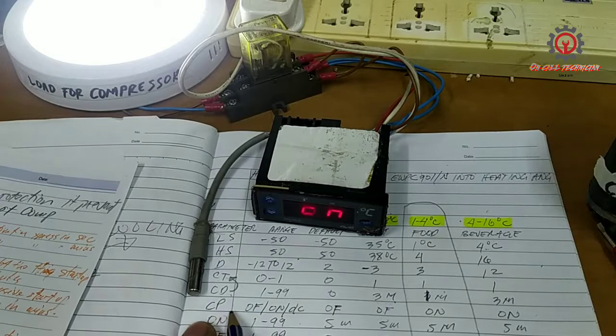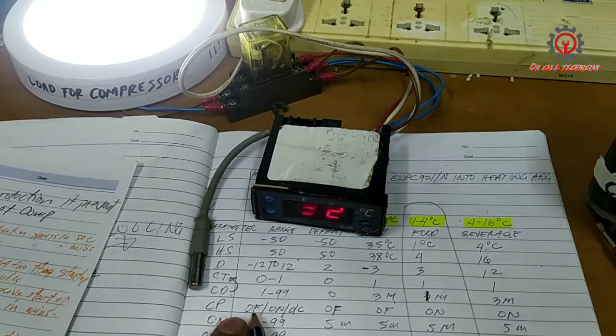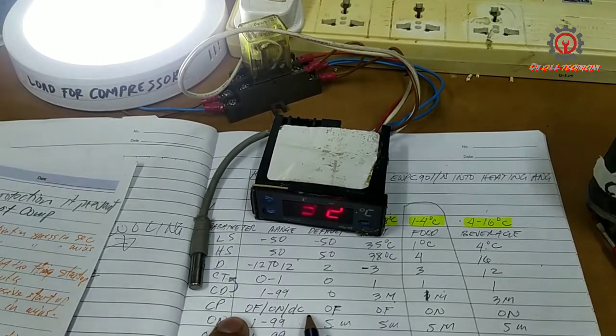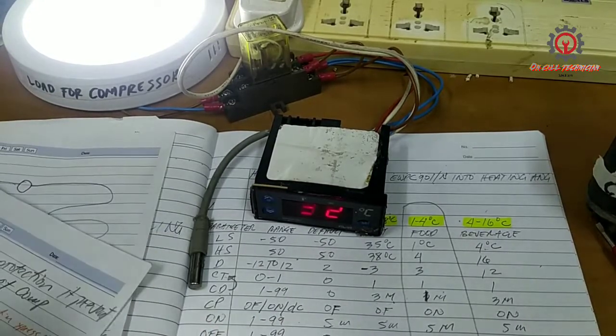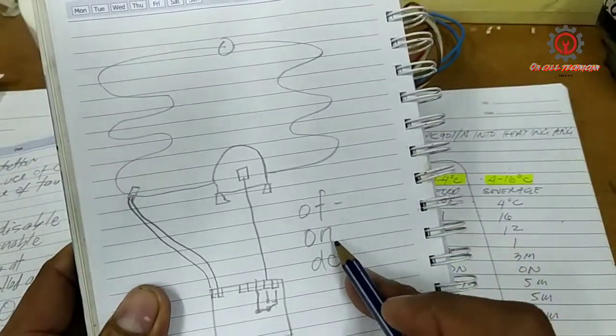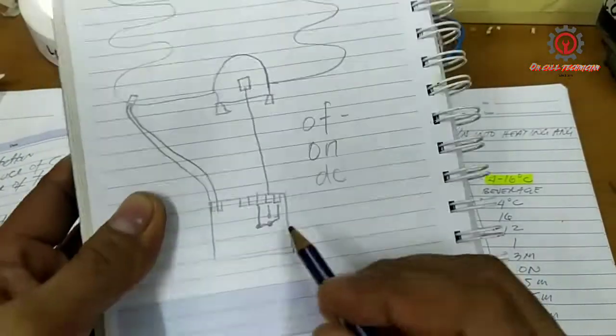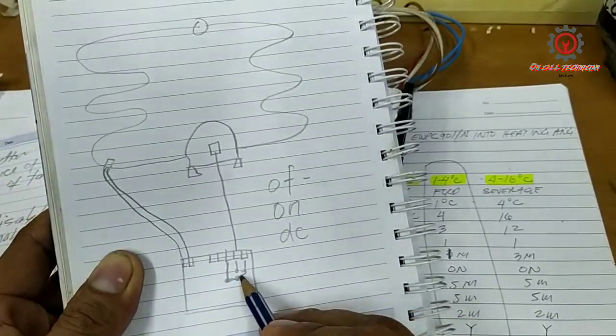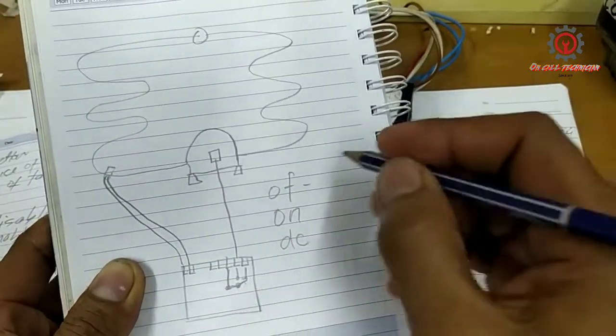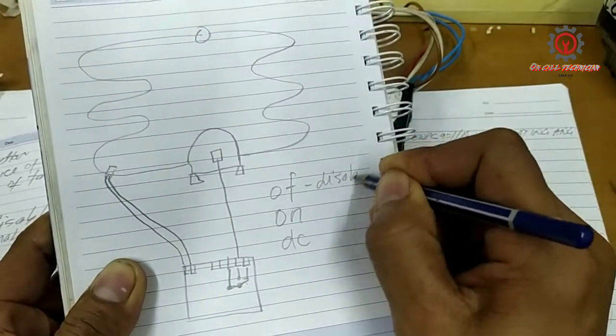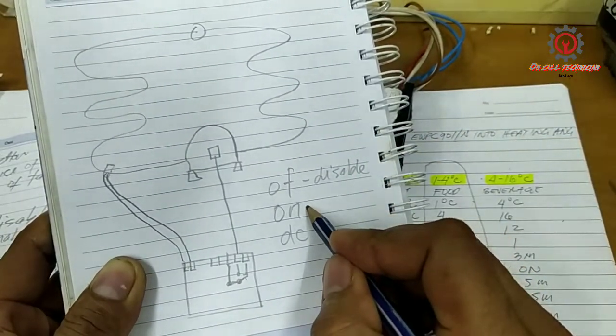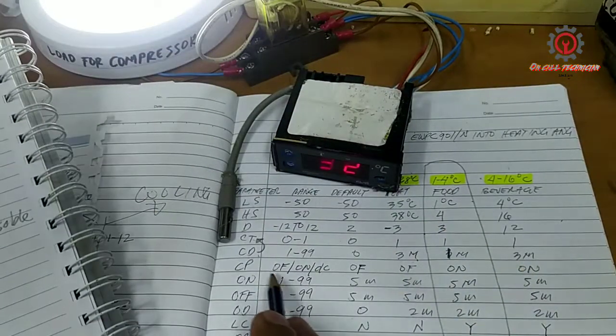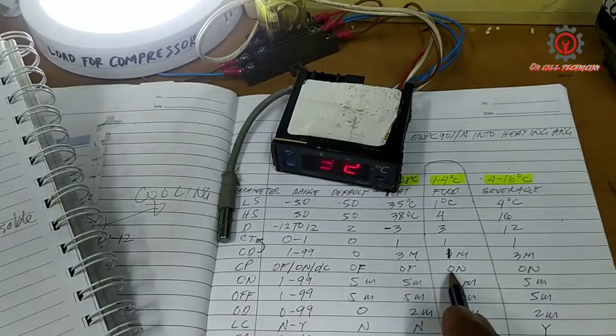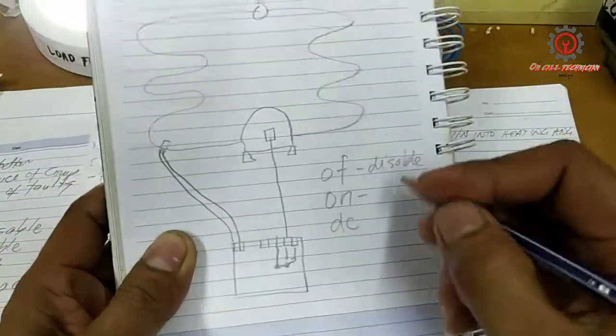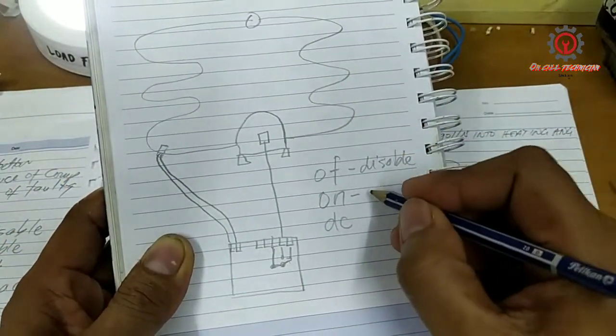Under CP we have a selection of OF, on, and DC. Okay, we have off, on, and DC, and this is our control. And this relay here, if we choose off, it's always disabled. Now that I choose on here, the relay is always enabled.